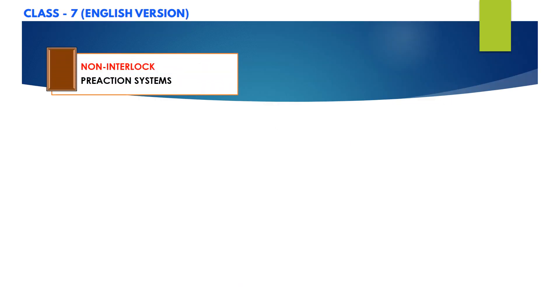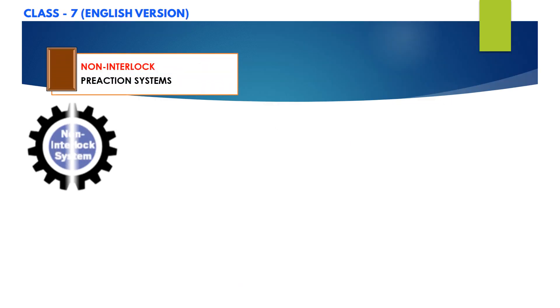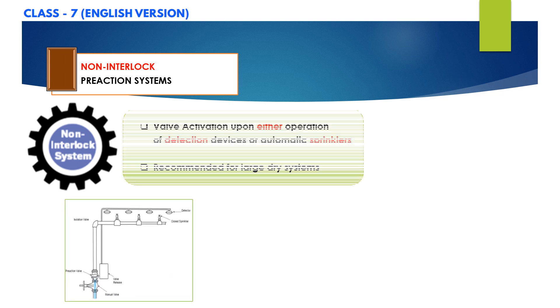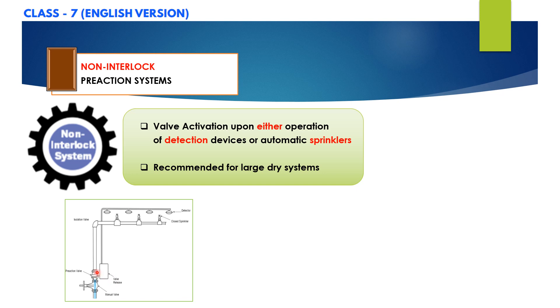Now let's discuss non-interlock pre-action systems. Non-interlock pre-action systems are designed such that the pre-action valve activates and admits water to the sprinkler piping upon either operation of detection devices or automatic sprinklers.